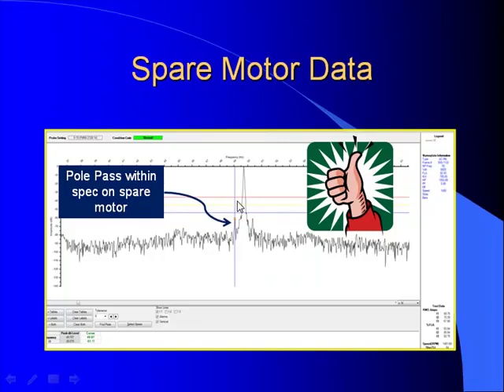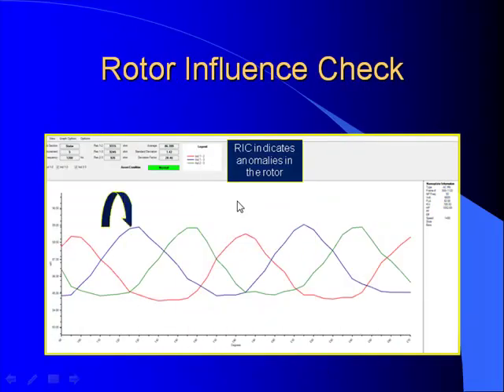Now, those previous two tests were online data. What about offline? What is this test telling us? This is a great and third piece of information to make this very difficult decision. 3 strikes and you're out, right? I like that call, yes. And if I was involved in this, knowing the cost that we're dealing with and the risk that we're making to yank this motor up from so deep, it's the right decision to make.